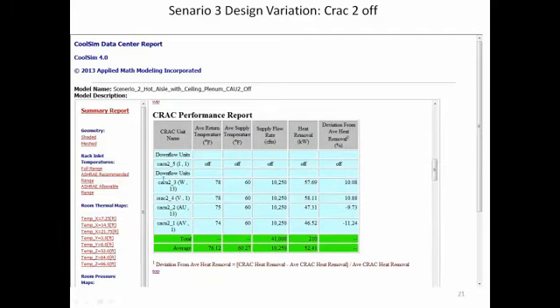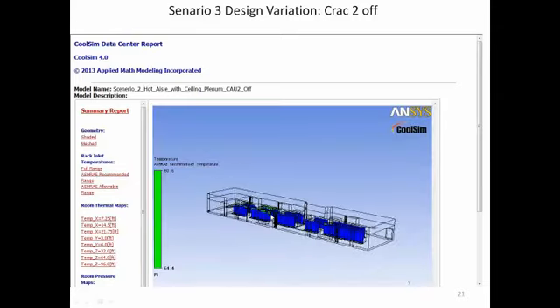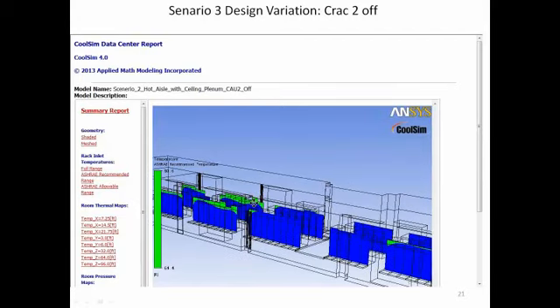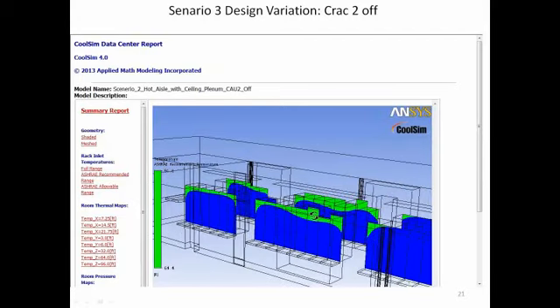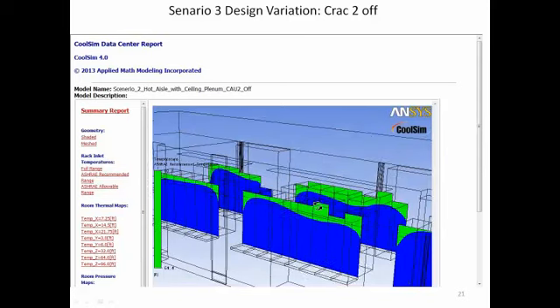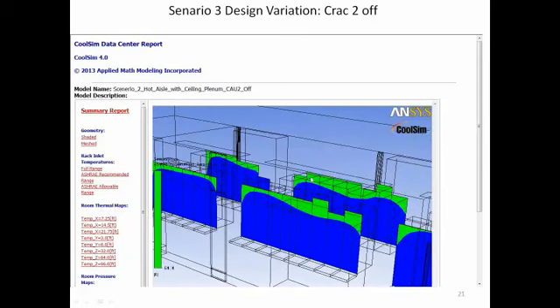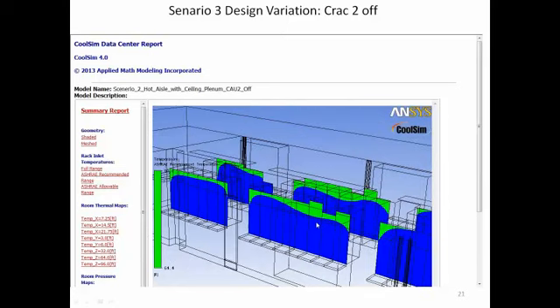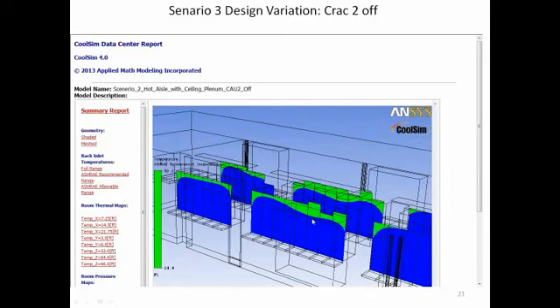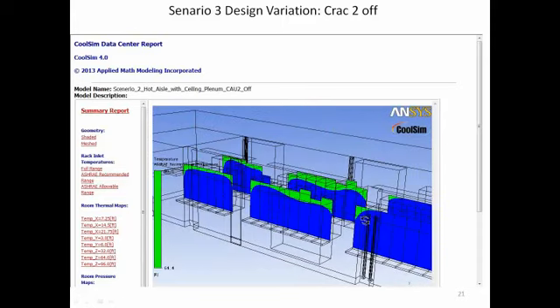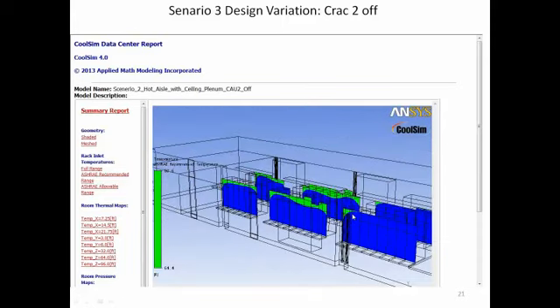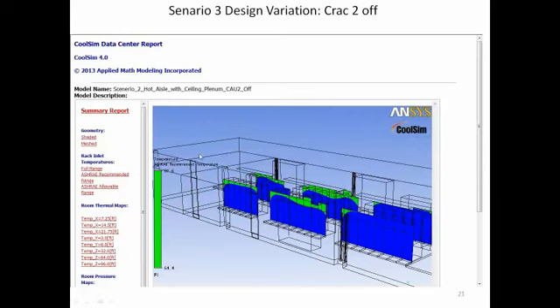And again, if we go and take a look at our recommended temperature inlets, they're all looking pretty good. Beginning to get a little bit of deviation. Again, it's within range, so no problem. Along the tops of these racks, which is not unusual, is where you see it near the top. And that's manageable in terms of where it is. And furthermore, there's opportunity here, I think, to move that supply temp up another few degrees. So this turned out to be pretty good.